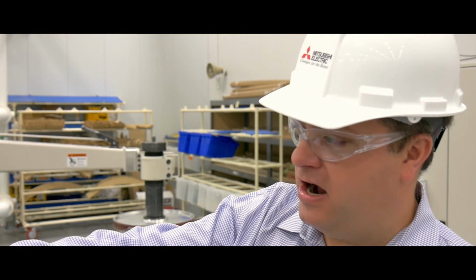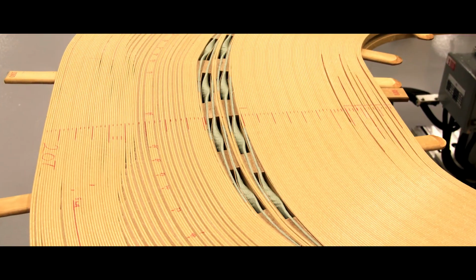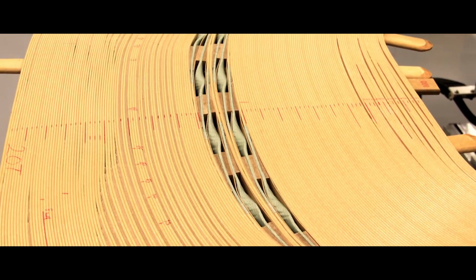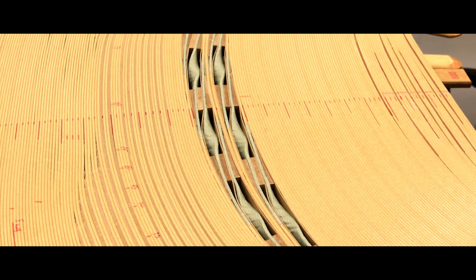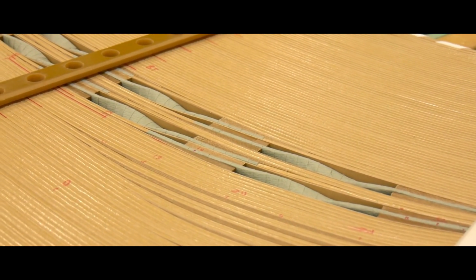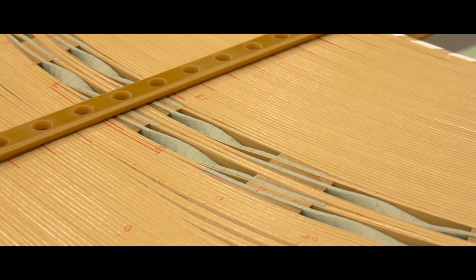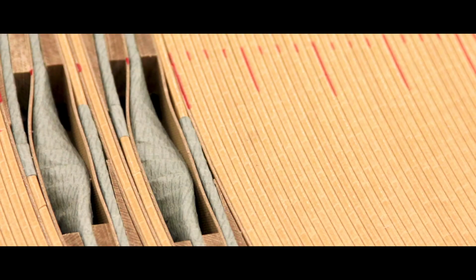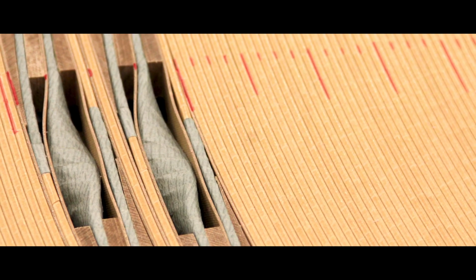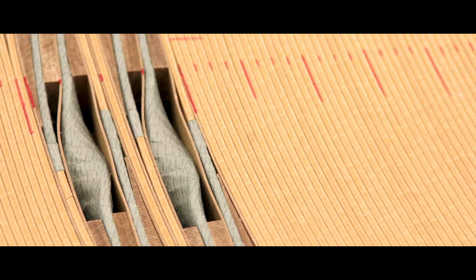Finally, another point to highlight is the transposition at the halfway point of each coil, individually designed per application based on the number of parameters and dimensions we're designing to. At the halfway point around the coil, we have a transposition that effectively cancels out circulating currents and magnetic fields inside each coil to prevent local overheating of the coils in service.